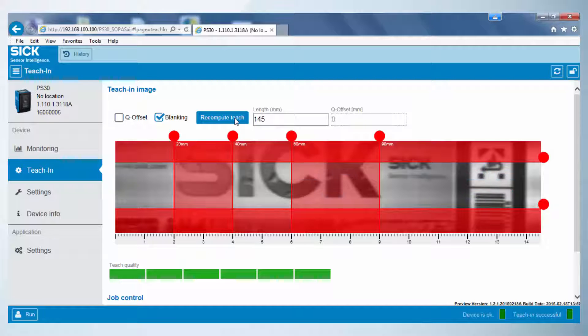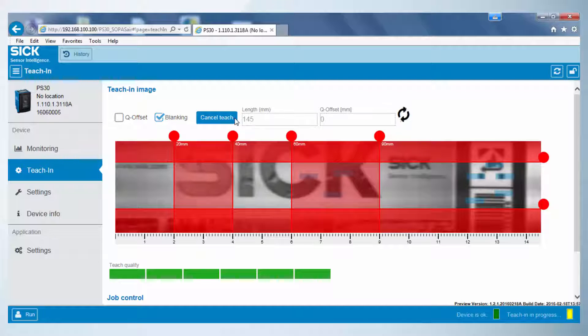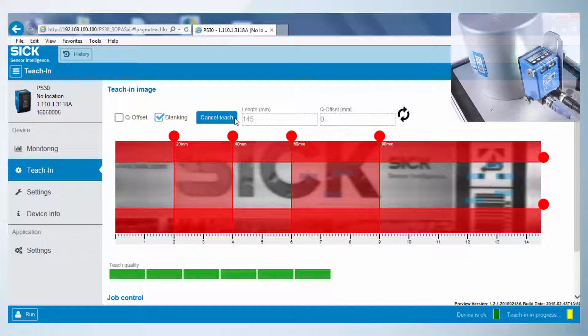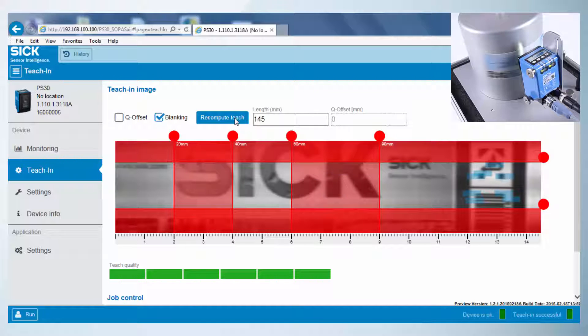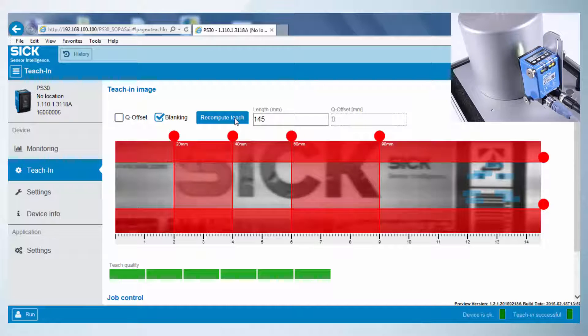In order to activate those areas, the Recompute Teach button has to be pressed and the label needs to pass the sensor a few times. As soon as the rotating arrow disappears, teach-in data is recalculated and the sensor gives a stable and accurate switching output considering the defined blanking and offset areas.